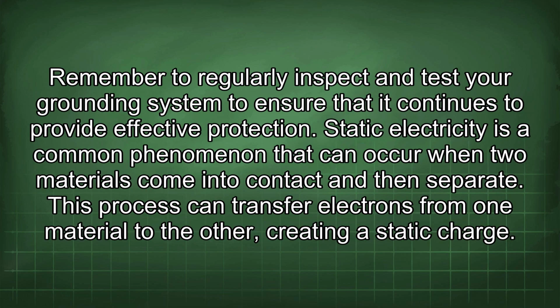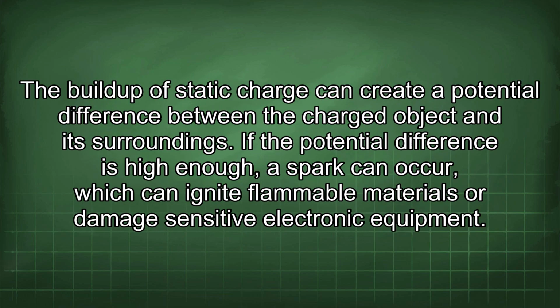Remember to regularly inspect and test your grounding system to ensure that it continues to provide effective protection. Static electricity is a common phenomenon that can occur when two materials come into contact and then separate. This process can transfer electrons from one material to the other, creating a static charge. The buildup of static charge can create a potential difference between the charged object and its surroundings.